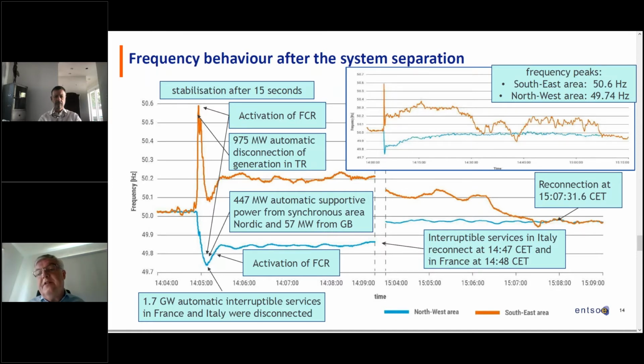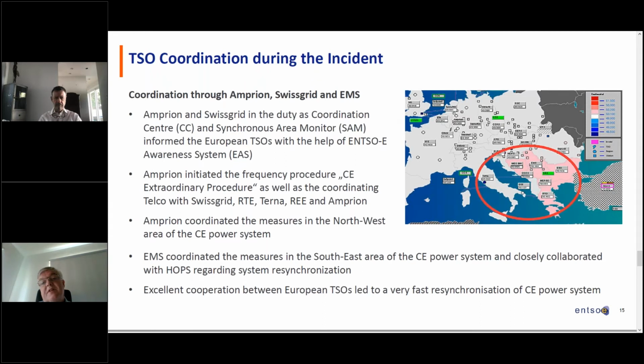Afterwards, we had a reconnection about one hour later. Both areas had to go back as close as possible to 50 hertz to be in as stable a system as possible, which allows reclosing the lines without them immediately taking on too much power again. If the frequency is close to 50, it means the area is balanced, meaning that when you put the lines back into service, they transport almost no power. This is the best way to reconnect the system, and all of this was coordinated in less than one hour.